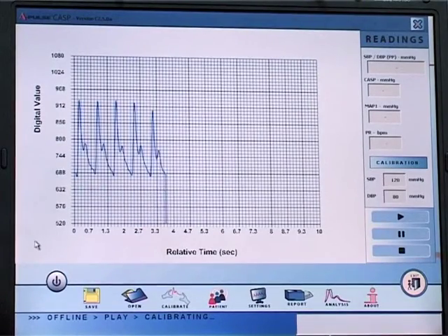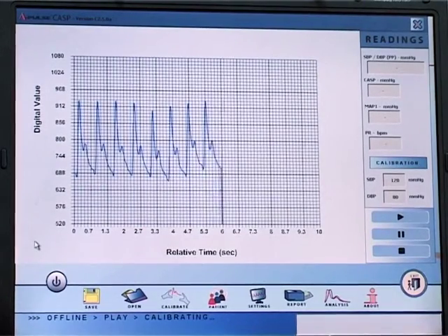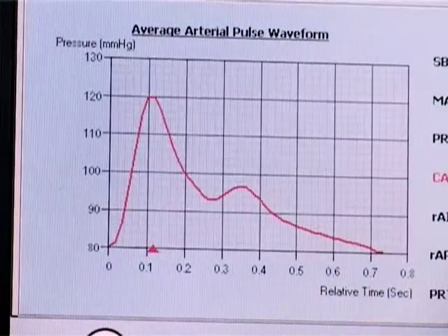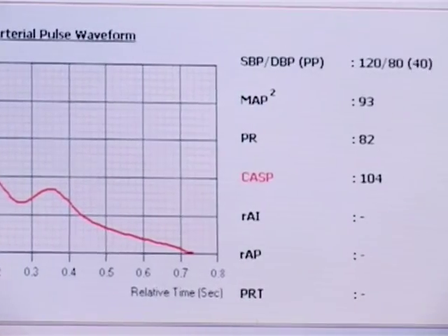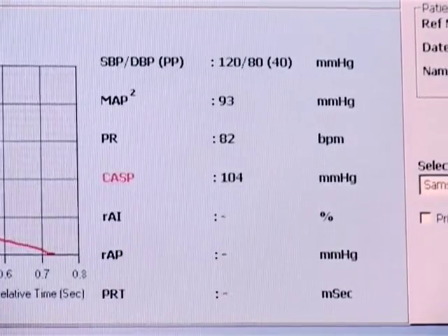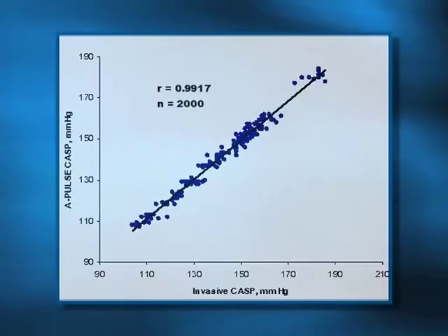Now, when we did that invasive method using a protocol written by Professor Brian Williams, he used a catheter and put it at the root of the aorta, and we put the B-Pro on the hand of the patient undergoing angiogram. For every wave, we continuously followed wave for wave. We measured the central pressure here, and we read off the central pressure as calculated by the A-PULSE.